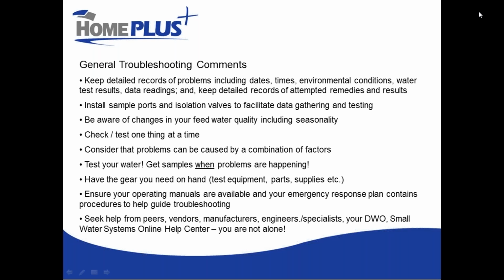So isolation valves might be appropriate to bypass certain treatment processes, but keep in mind that that will generally not be permissible to bypass any form of disinfection process or a process designed to remove a health-oriented contaminant like arsenic or uranium or something like that. So isolation valves that allow us to bypass a piece of equipment temporarily that's not related to health protection.